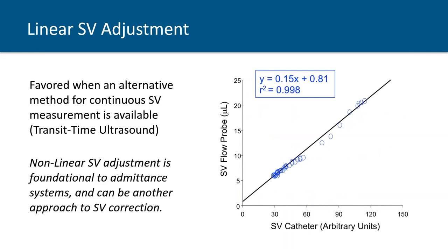And here, when you plot the stroke volume from the flow probe against the stroke volume from the catheter, you do a linear regression, if it's a reasonable linear fit, which in most cases it was in our studies. And then you come up with the slope of this line, which in this case was 0.15. And this 0.15 now will be your calibration factor that you can apply to correct the stroke volume measurements from your catheter.